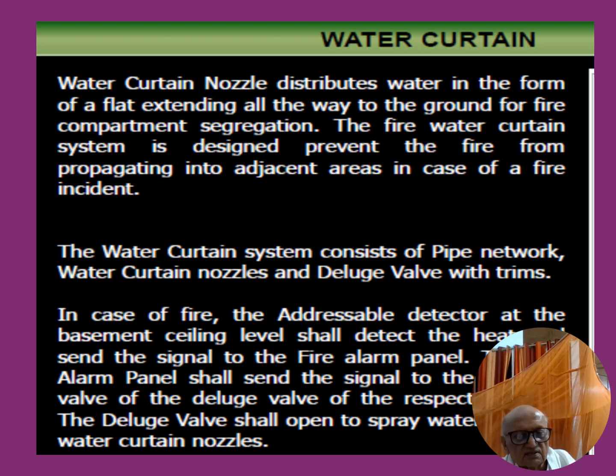In case of fire, the addressable detector at the basement ceiling level shall detect the heat and send the signal to the fire alarm panel. The fire alarm panel shall send a signal to the actuating valve of the deluge valve in the respective area. The deluge valve shall open to spray water through water curtain nozzles. Friends, this is all.